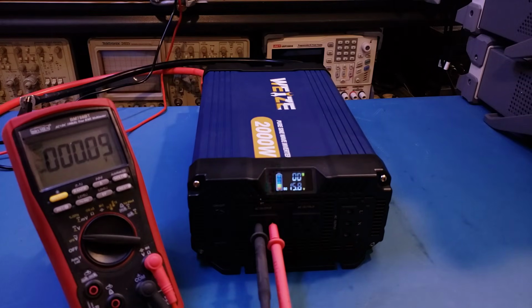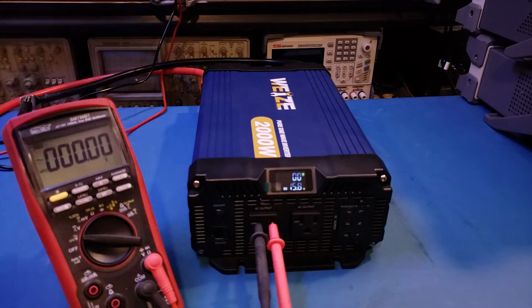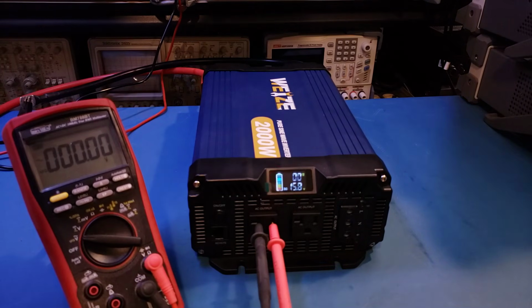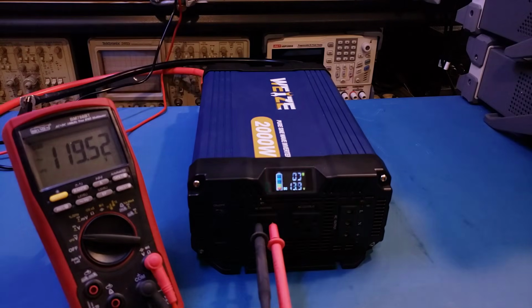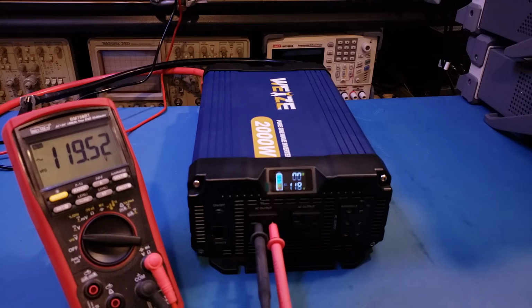So right now we exceeded the upper voltage limit, and you can see the output gets cut off immediately. The behavior here is actually slightly different than the under voltage protection. Let's see if it recovers if we drop the voltage. Yep, it recovered with no problem.